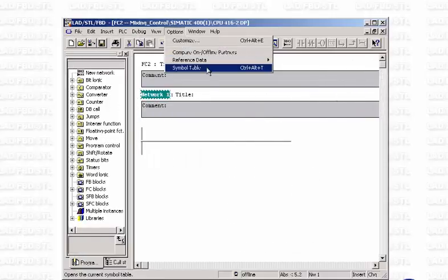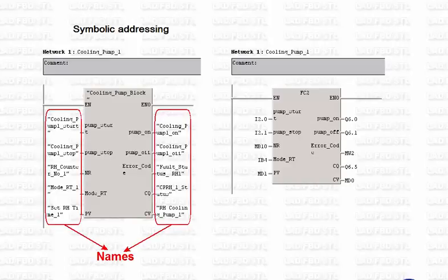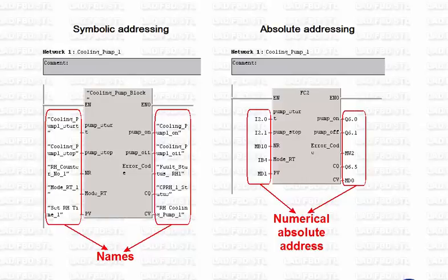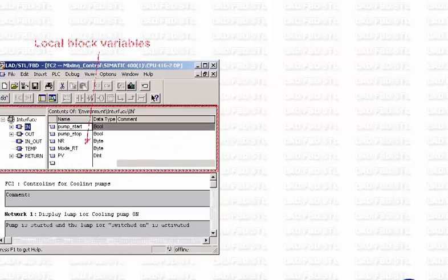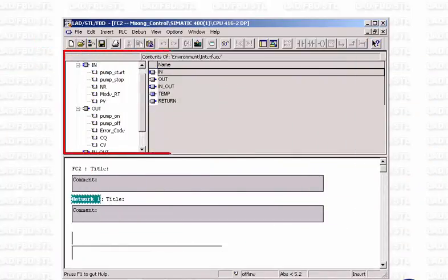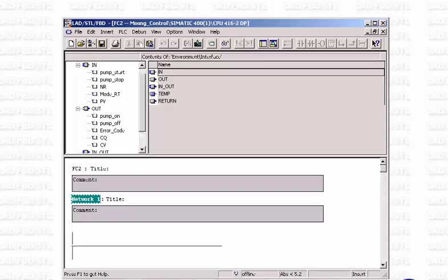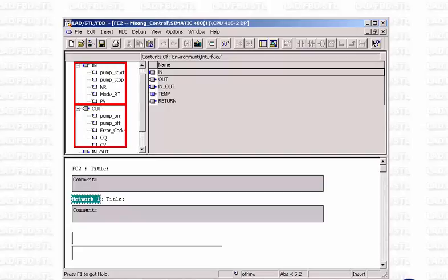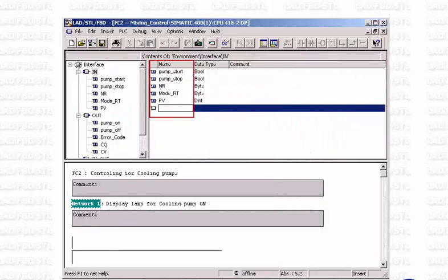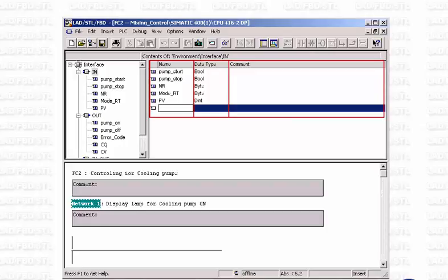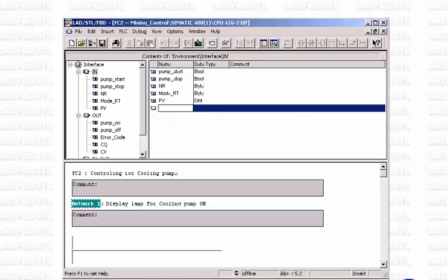To make programming even easier, the program editor offers the possibility to assign symbolic addresses to the operands and variables used in the program. Symbolic addressing uses names instead of the numerical absolute address, making your program more easily readable. With the program editor, you can edit the symbolic addresses of both block-specific and program-wide, globally valid variables. All variables used within a block can be created quickly and comfortably in the variable declaration table. They are referred to as block-local variables, such as input and output parameters or local data used in the block. These variables consist of the name, the data type, an optional comment, and also, where applicable, an initial value that is used when the block executes for the first time.